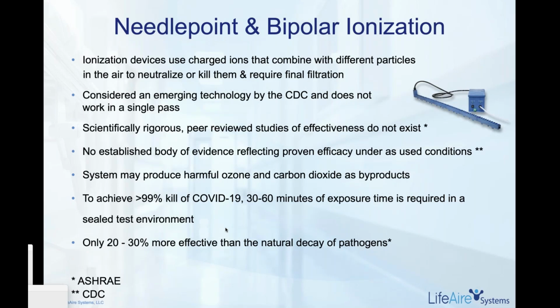You've probably heard a lot about bipolar or needlepoint ionization. Again, not a new technology, but it basically uses charged ions that combine with different particles in the air to neutralize or kill the particles. And again, this requires final filtration to capture the charged particles. It's considered an emerging technology, but does not deliver on a single pass. And we'll discuss this further, what we mean by delivering or killing on a single pass. And again, to achieve greater than 99% kill of COVID, it requires 30 to 60 minutes of exposure time. Per ASHRAE, this technology is actually only 20 to 30% more effective than the natural decay of pathogens.